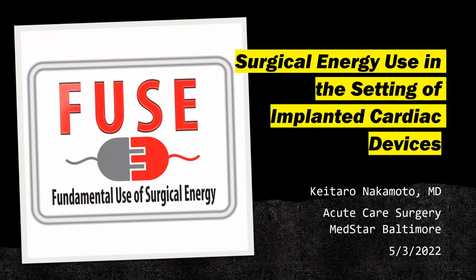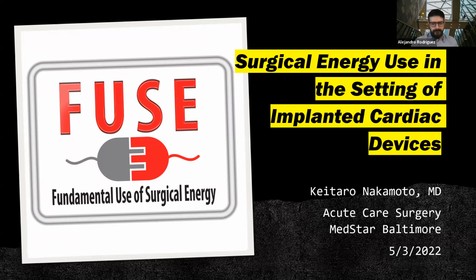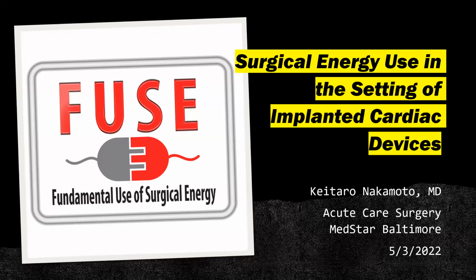The bipolar device is actually passing current, electricity, between the two jaws. Now this electricity is an enormously low voltage current going across there. We talked about how 30 watts coag has 9,000 volts. High voltage sets us up for stray energy.